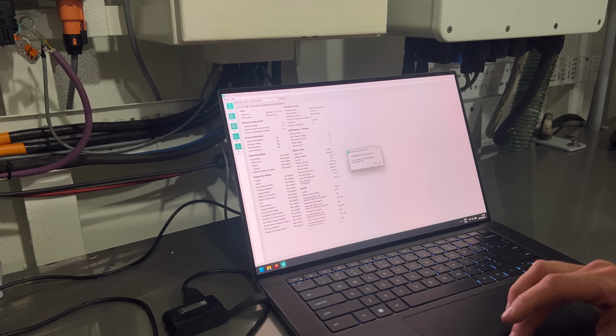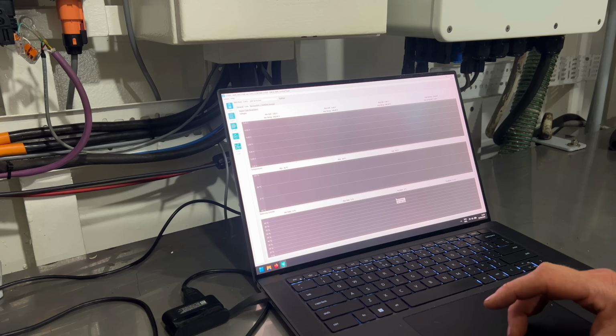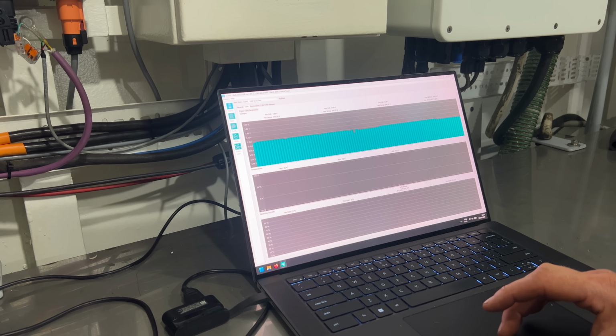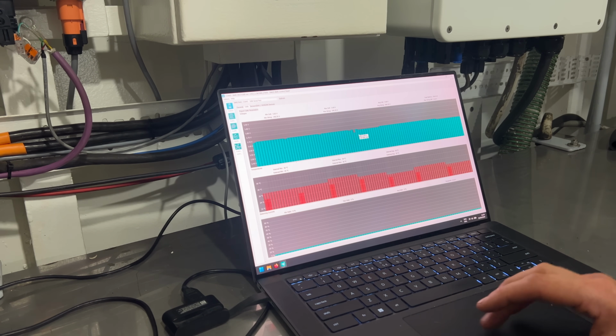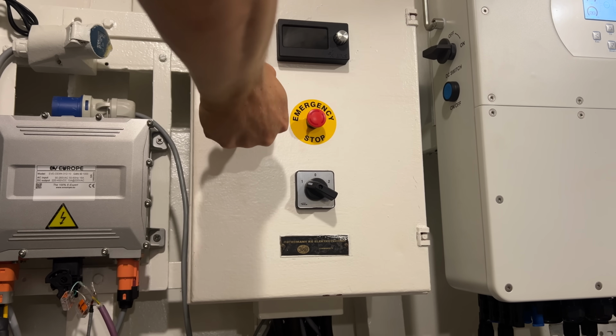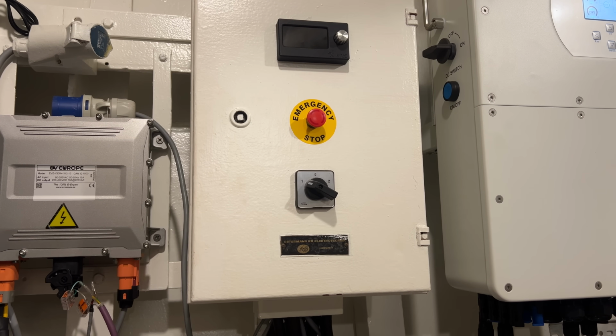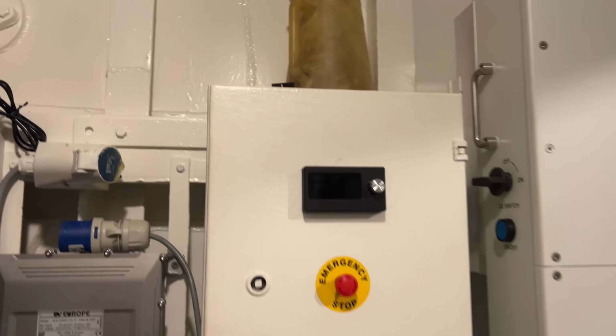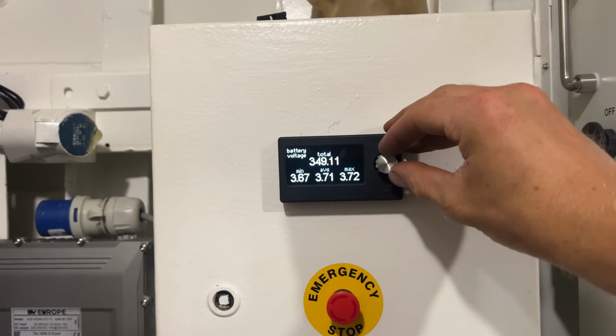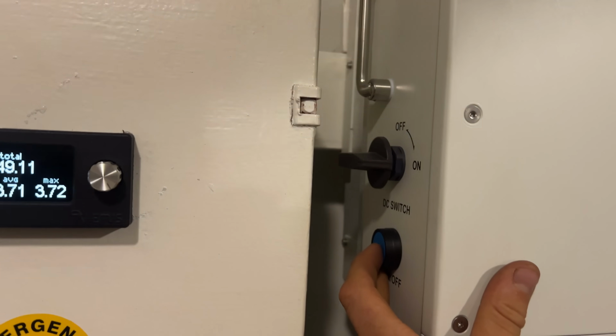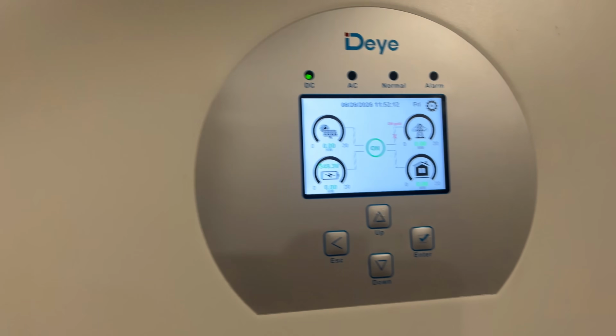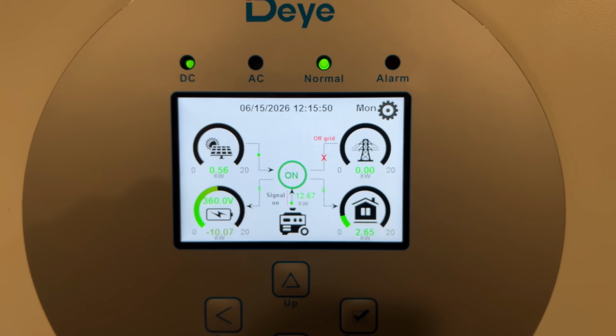It took some tinkering, but we eventually got working communication between my laptop, the BMS and the battery. And I can read out everything about each individual cell. And also here I can check and change the safety values for temperatures and the charger and all that stuff. It all looks good. So if I close the door of the cabinet, the safety interlock loop closes, so the BMS gets green light to power the high voltage DC bus. That means the hybrid inverter is also connected to the system. So we can see if it does what it should. And we can check if the generator charging works as well.